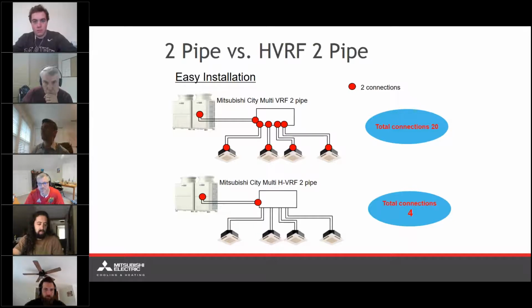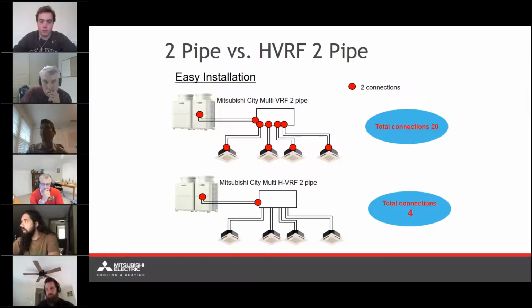So for this particular, on the top layout, where it's just a standard heat recovery system, 4 fan coils, we're looking at 20 different braze points. It's 2 connections at the condenser unit, 2 connections at the BC, and 2 connections for each port and each fan coil. That adds up. But ultimately, you're going to be reducing that. Everything downstream of the HBC controller is going to be water piping. The only braze points are between condenser unit and the HBC controller.